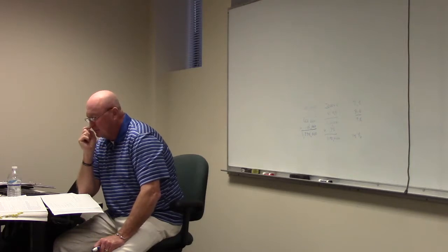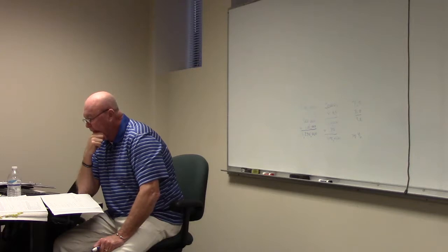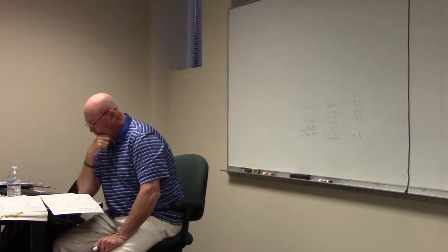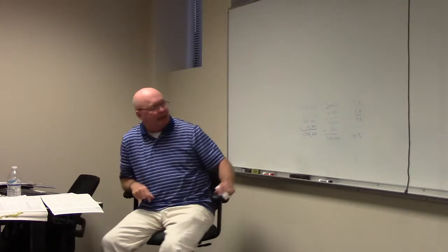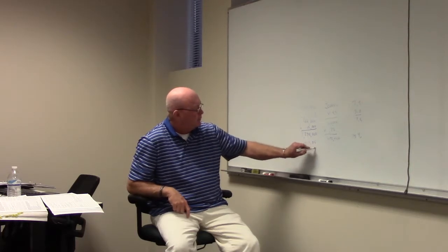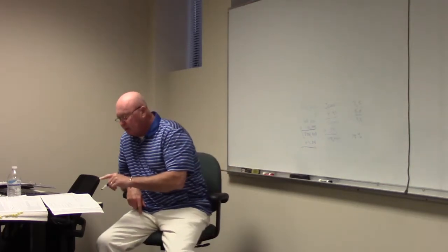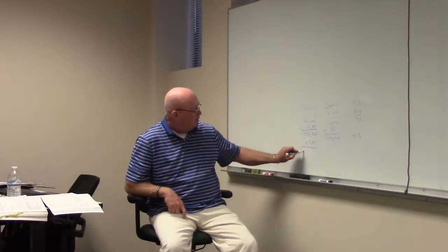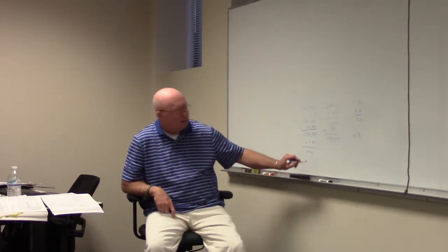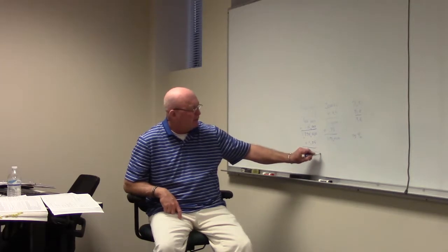It talks about continuous load. In a school, that's probably what we're going to have, aren't we? So what they've done is they've taken this whole thing and multiplied it times 1.25. And we see that we get 1,593,750 VA.